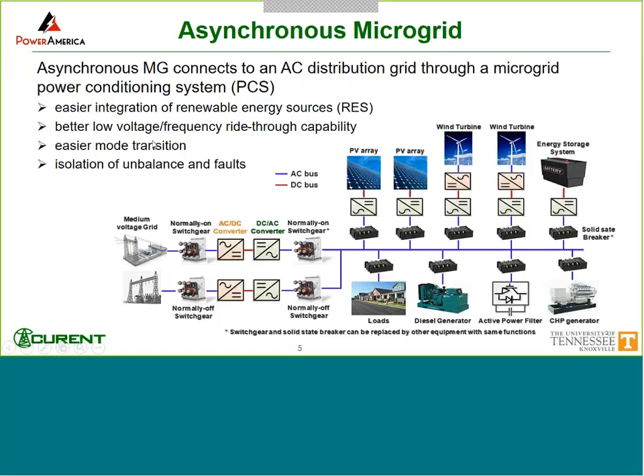it will provide better ride-through capability, either low voltage or low frequency. And also the mode transition will be easier from grid connected mode to islanded mode or vice versa. And because of this link in between, it actually will allow abnormal conditions such as unbalance and faults to be isolated from each other between the microgrid and distribution grid.